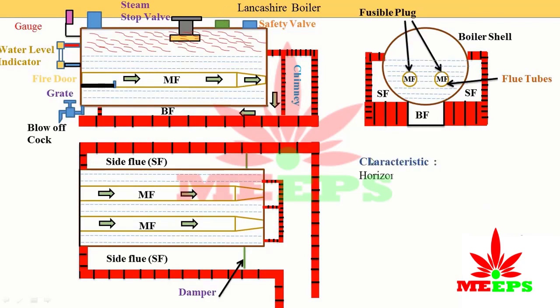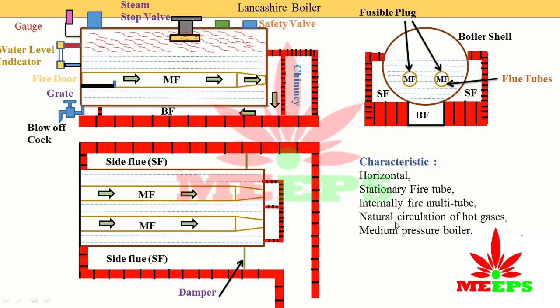Key characteristics of the Lancashire boiler: it is horizontal because its shell is horizontal. It is a stationary fire tube boiler — fire is inside the tube, and stationary means it is not movable. It is internally fired because the furnace is inside the boiler. It is multi-tube because more than one tube — specifically two tubes — is used. Lastly, it has natural circulation of hot gas, meaning the hot gas produced in the furnace is naturally circulated through the boiler and brick construction with no blowers. It is a medium pressure boiler.